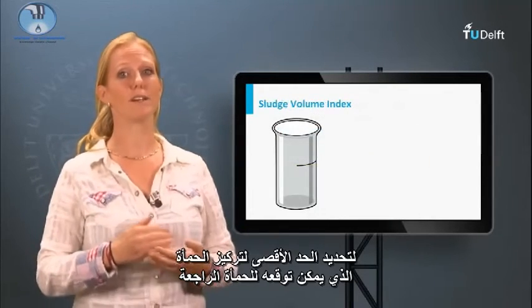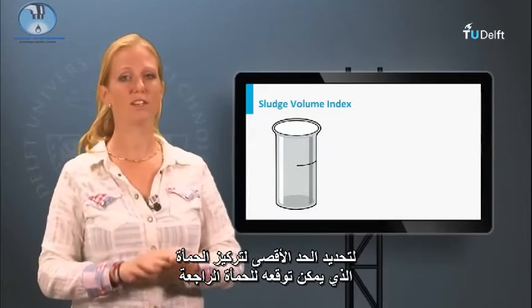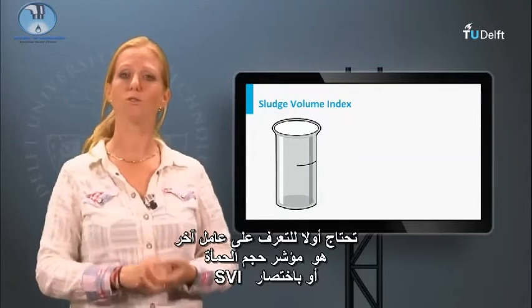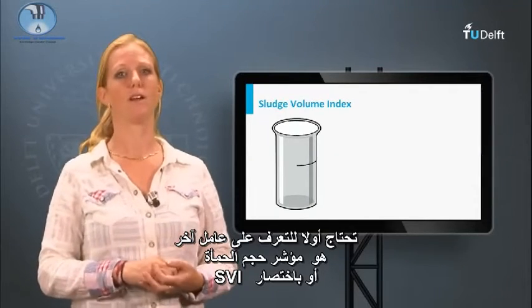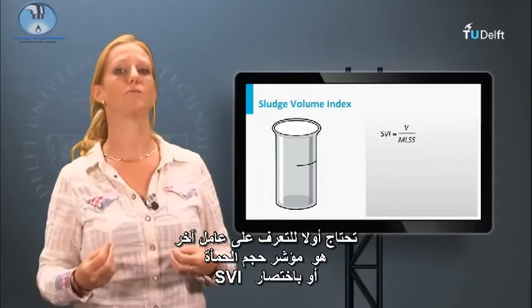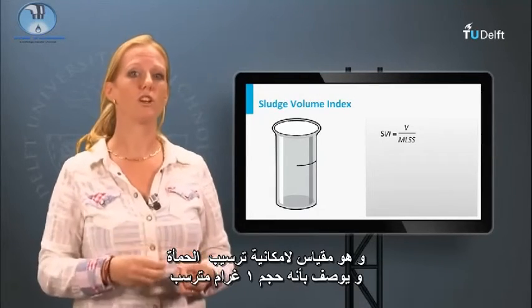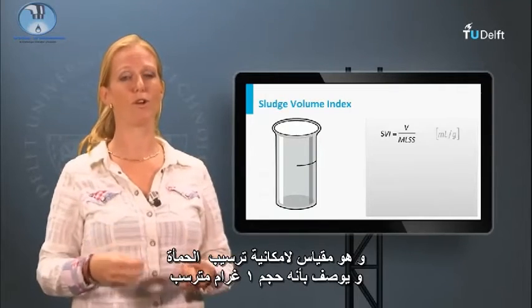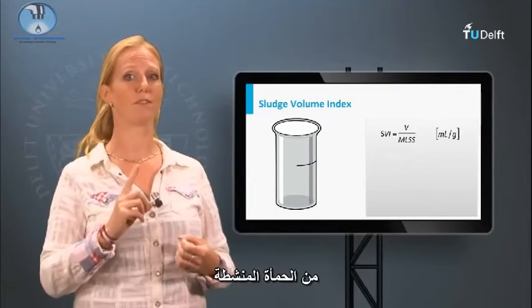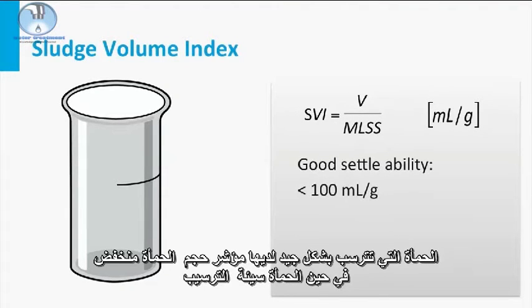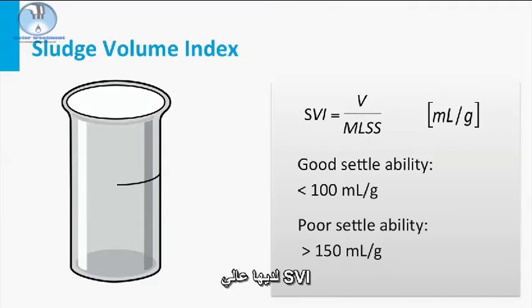To determine the maximum sludge concentration that can be expected in the sludge recycle, you first need to be introduced to another parameter, the sludge volume index, or SVI in short. This is a measure for the sludge settlability and is described as the volume of one gram settled activated sludge. Sludge that settles well has a low sludge volume index, while poorly settling sludge has a high SVI. The latter is known as bulking sludge.